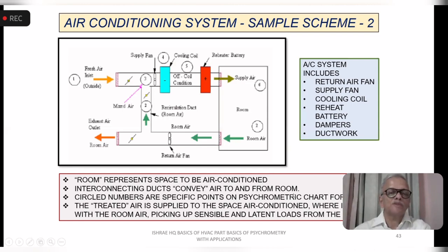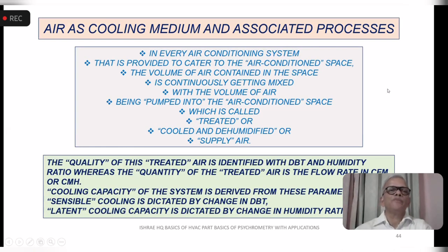The circled numbers are the specific points on the psychrometric chart for analysis. Whatever you see, one means the outdoor air condition. Two is the return air. Then one and two get mixed, and you have this mixed air condition passing over this cooling coil. Then this is the off-coil condition. Then if you have a heater arranged, that is where your psychrometric process will come. This air system includes these components, which are shown here. So this shows the circulation of air with the properties of air identified at the specific locations which are being measured.